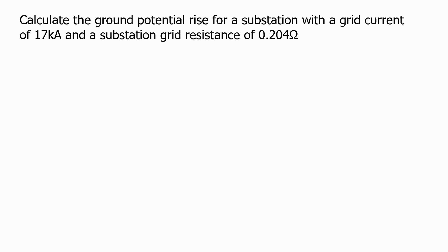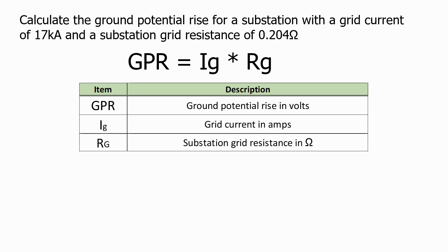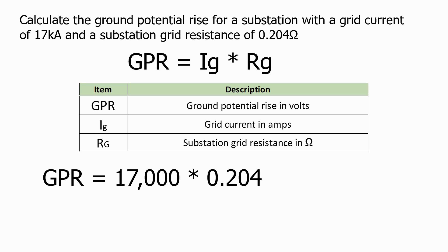Let's do a worked example. Calculate the ground potential rise for a substation with a grid current of 17kA and a substation grid resistance of 0.204 ohms. Using our formula, the ground potential rise equals the grid current multiplied by the substation grid resistance. Putting the figures in, we have a GPR for this substation of 3468 volts.